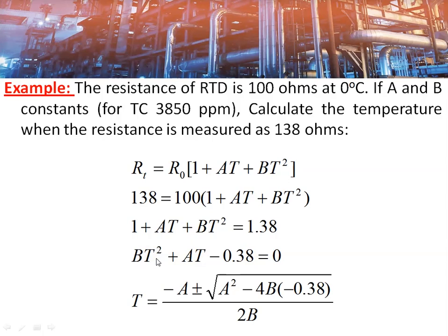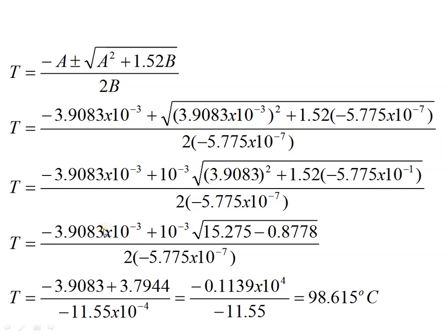This is a quadratic equation of the form ax² + bx + c = 0, whose solution is given by (−b ± √(b² − 4ac)) / 2a. Applying the same here, the temperature is given by: (−A ± √(A² − 4B × constant)) / 2B. Solving this equation, the temperature corresponding to 138 ohms is 98.615°C. If the resistance is 138.5 ohms, the temperature comes out to 100°C — confirming that at 100°C the resistance is 138.5 ohms.